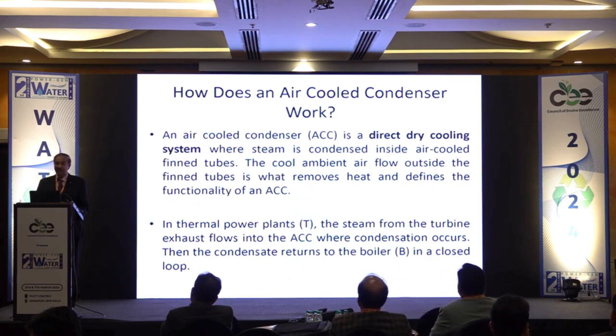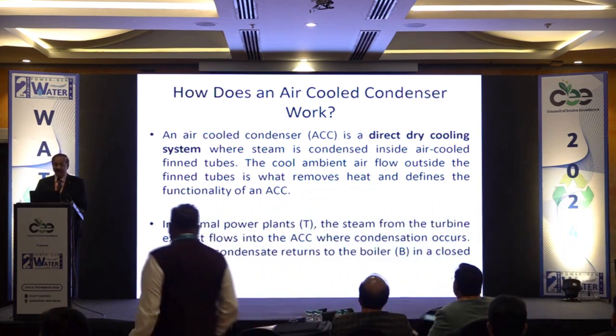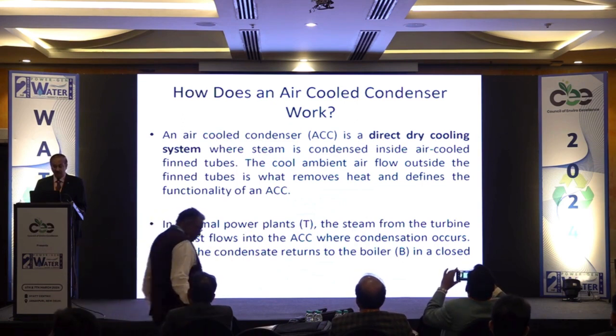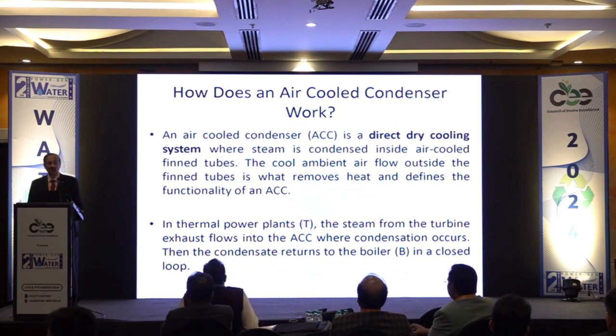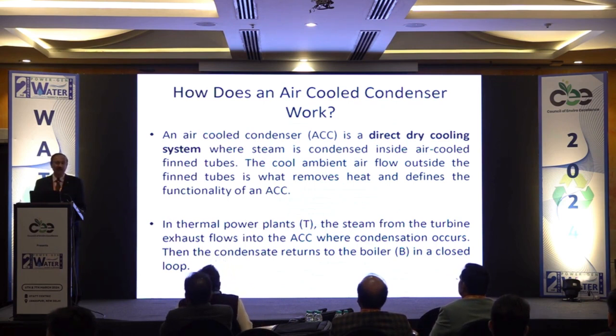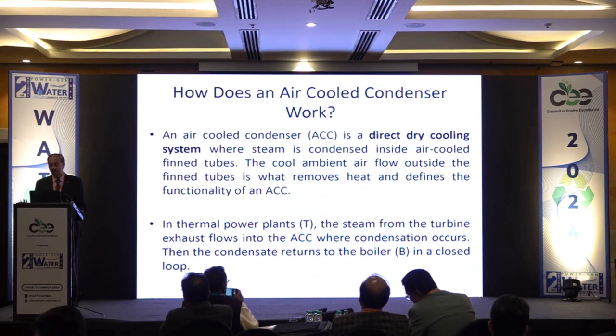So let's see, how does an air-cooled condenser work? An air-cooled condenser is a direct dry cooling system where steam is condensed inside air-cooled finned tubes. The cool ambient air flow outside the finned tubes is what removes heat and defines the functionality of an ACC. Those who have worked in a gas power plant also know that in a gas power plant we have what is called fin fan coolers. Fin fan coolers are again something of a similar type, whereas in basically equipment cooling and other cooling we have water-based coolers. In gas power plants we have air-cooled coolers. So similarly, ACC is a bigger version of the same.